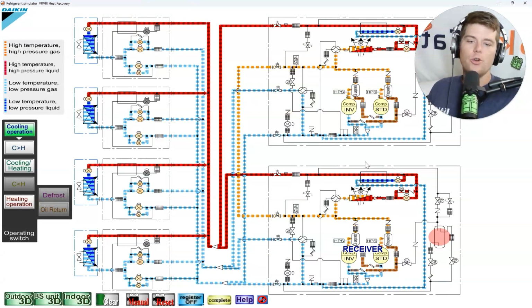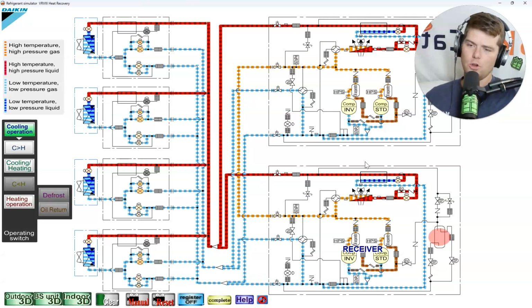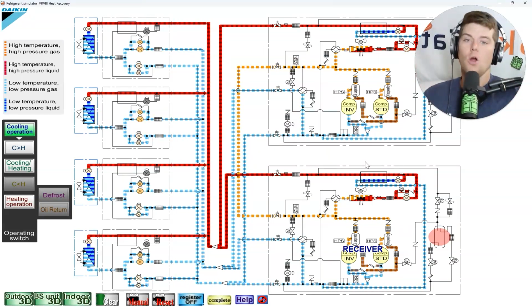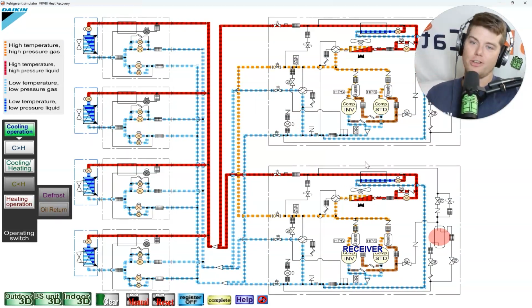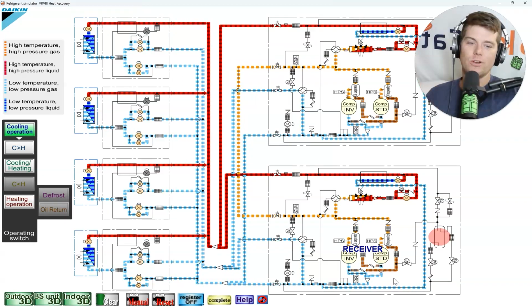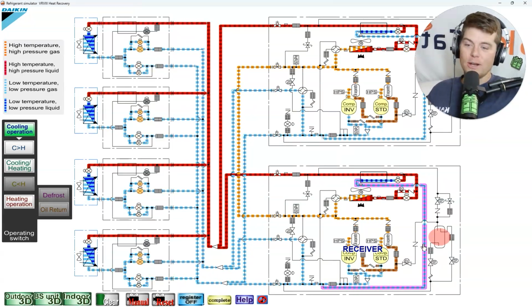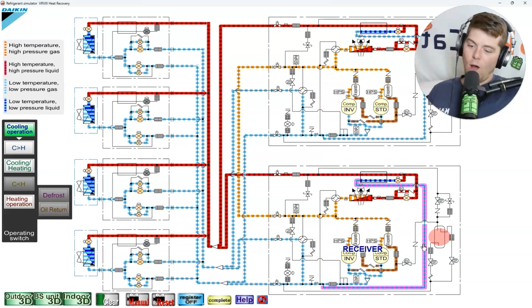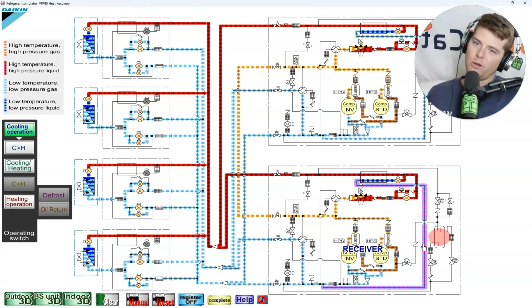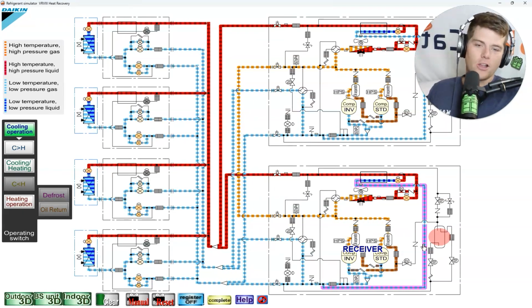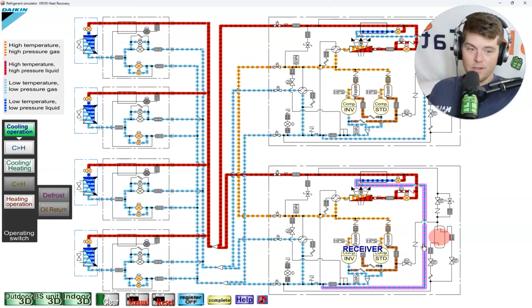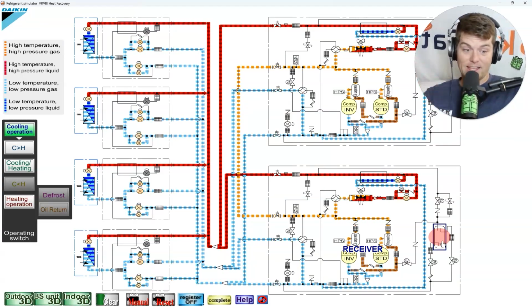And so what do you do on a 20-ton system when only 2 tons of cooling is actually calling for capacity? Well, what you do is you take that refrigerant and you stack it in your liquid receiver. Again, Brian Orr did a podcast on why subcooling doesn't matter when you have liquid receivers in systems. Now you're going to say, well, that contradicts everything we teach here. And again, he has a point up to a point when it comes to VRF. And that point is exactly this.